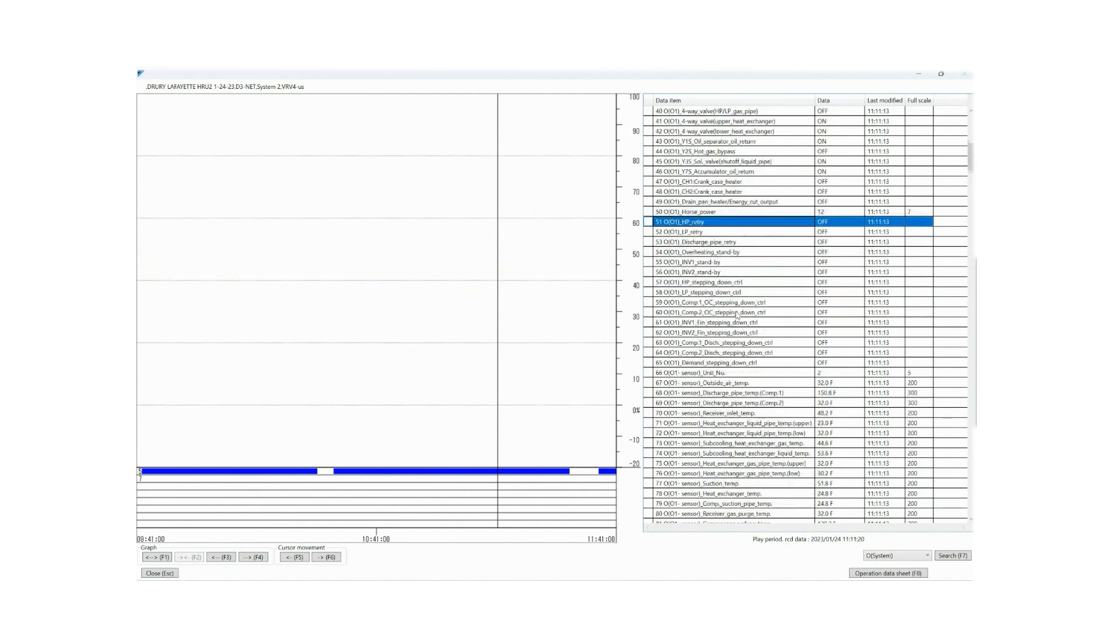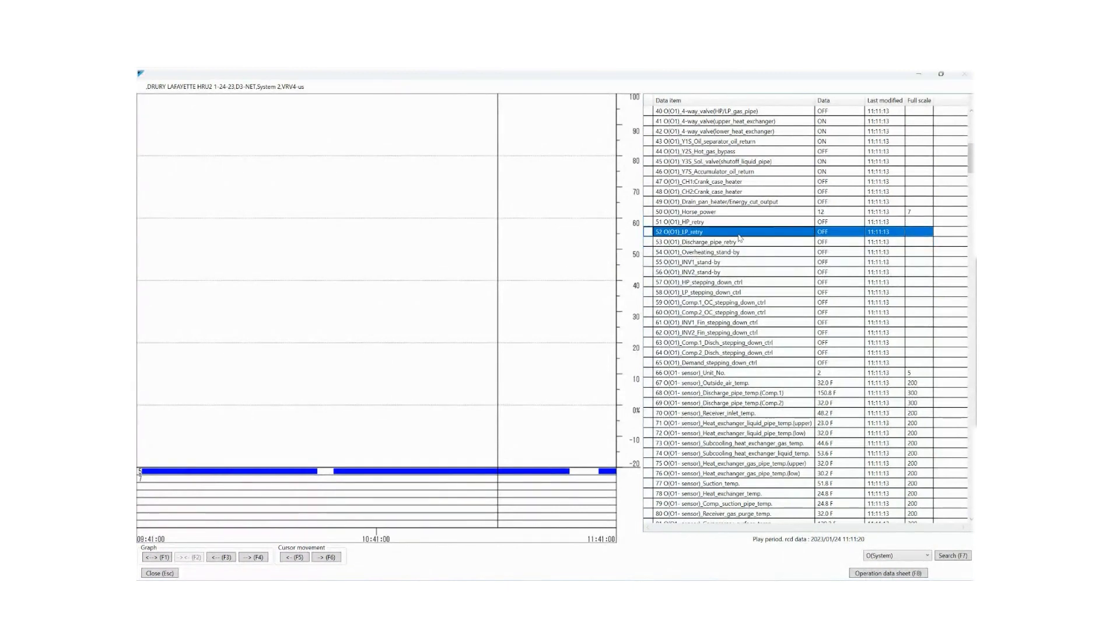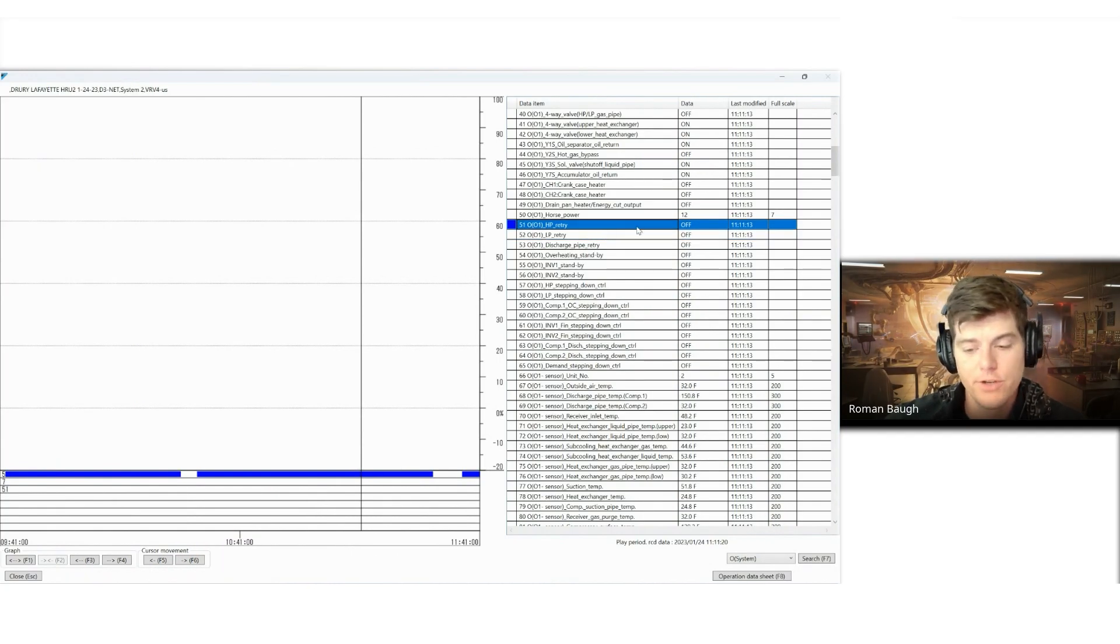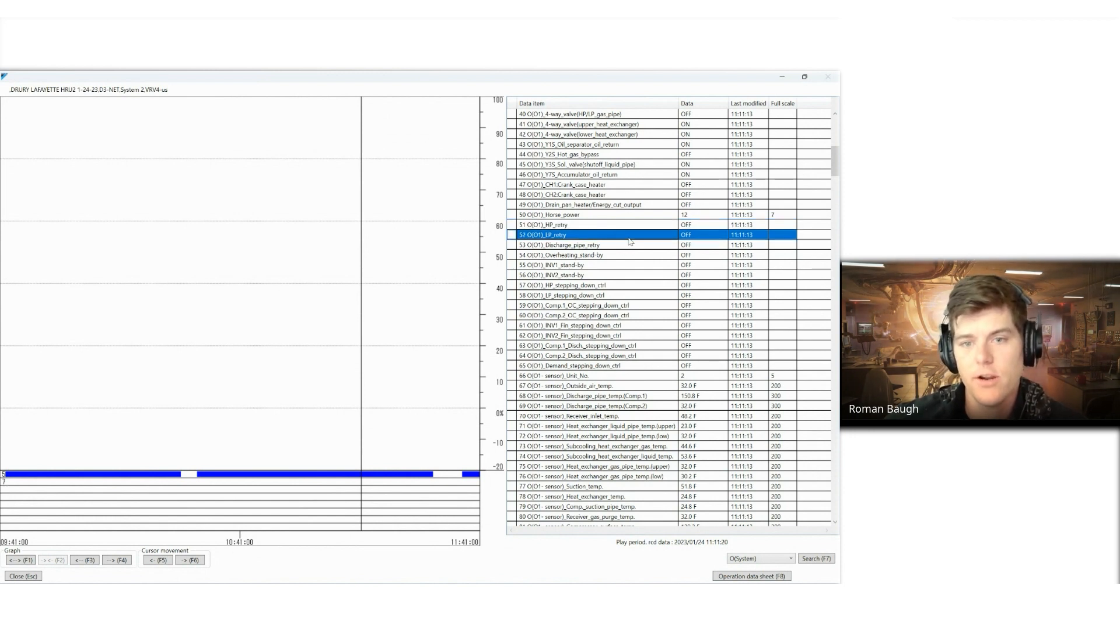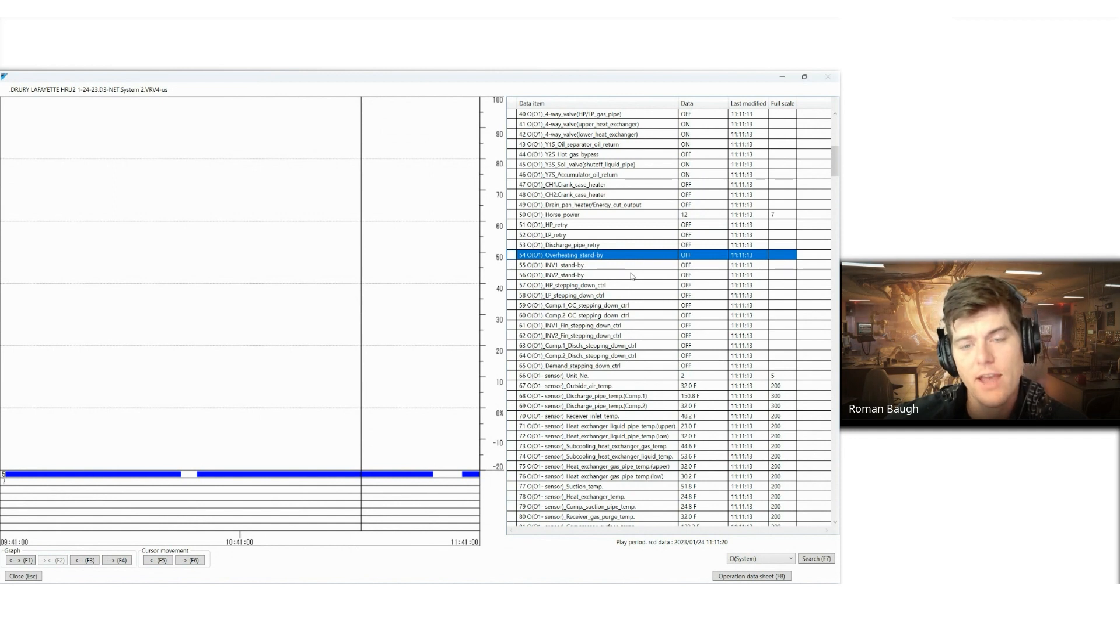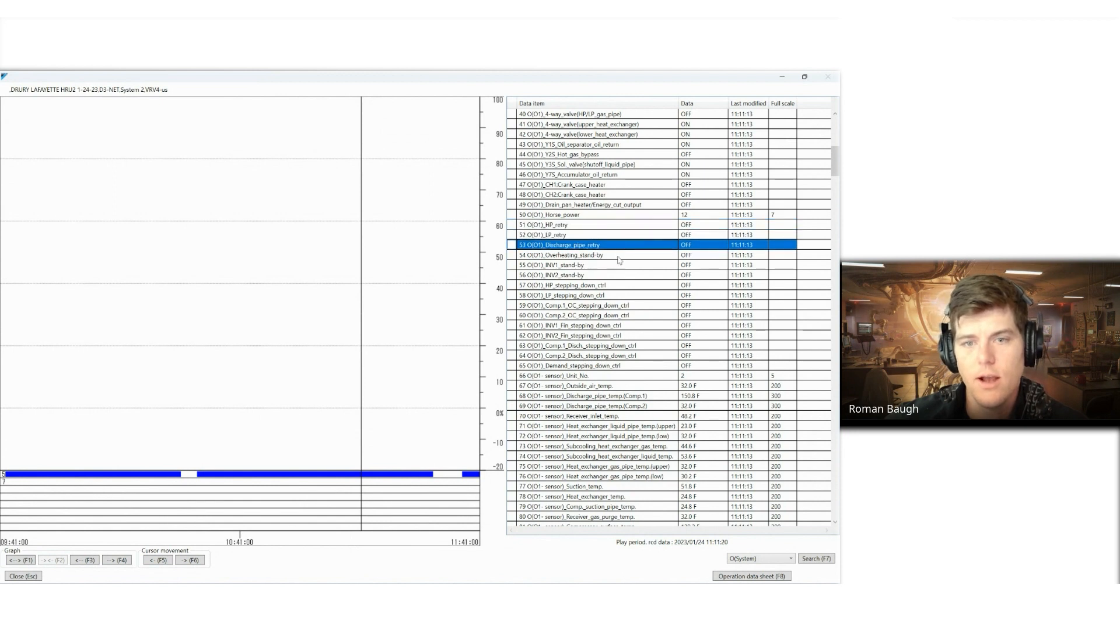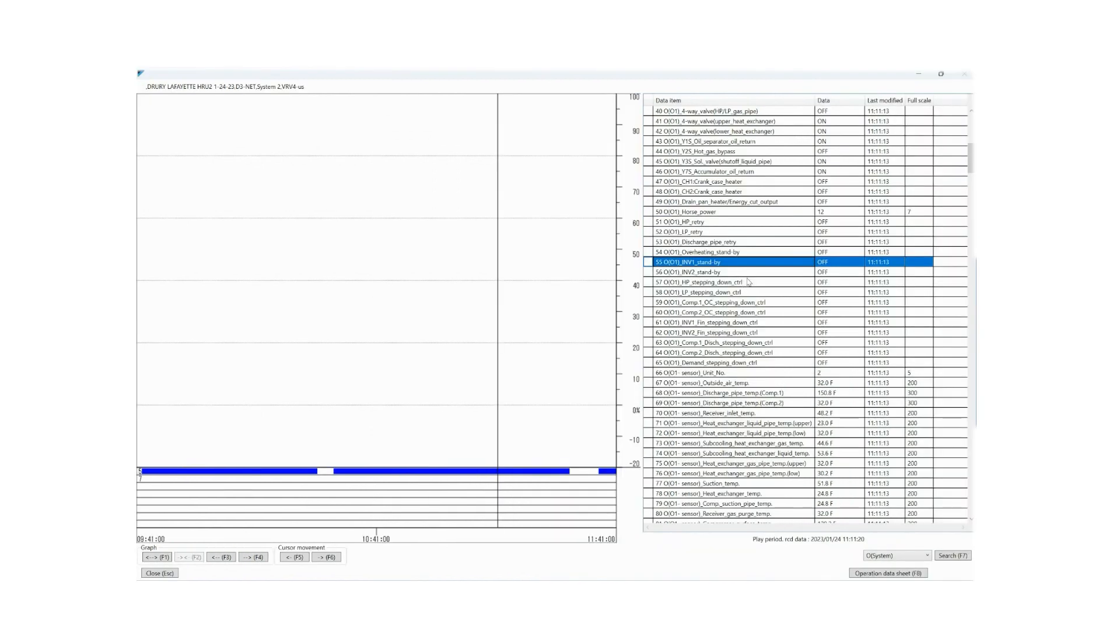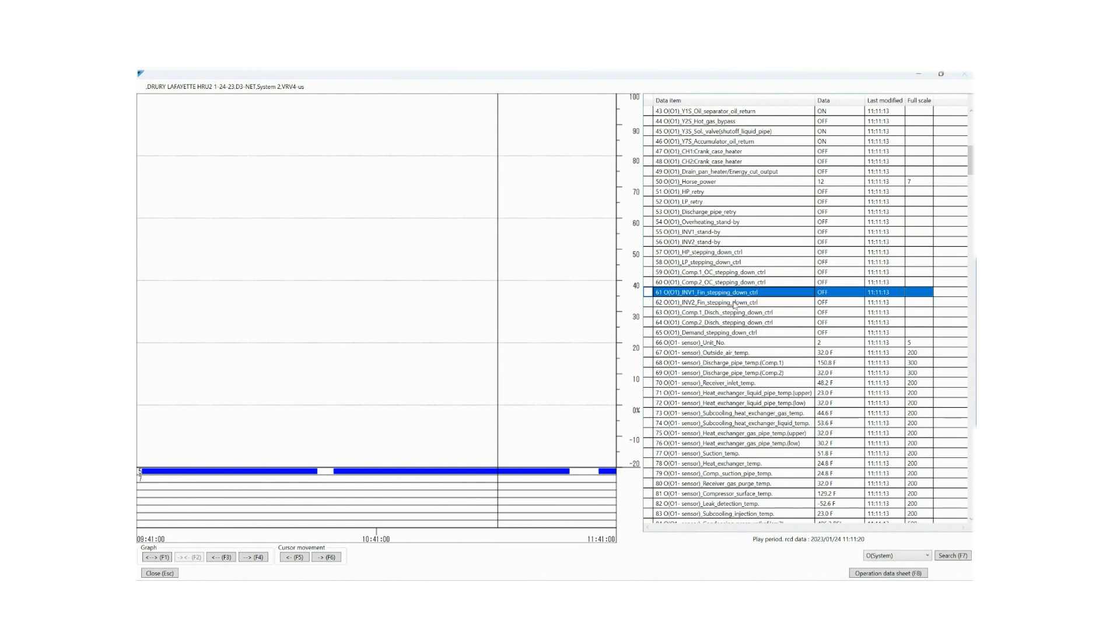Then we get into your safeties. High pressure retry, low pressure retry, discharge pipe retry. These are all of your safeties that may energize if the system hits the necessary window or time frame where something like this will apply. And so I can plot this on my graph here on the left-hand side and say, it went into high pressure retry three times before it threw a high pressure error code. That's something that I can actually see through service checker. These are basically safety controls saying, there's an issue. I'm going to step down and try again. And if there's an issue again, three times in a row, I'm going to generate an error code. You can watch that unfold through these little on-off safeties that you see here. Inverter standby one, standby two, high pressure step down.